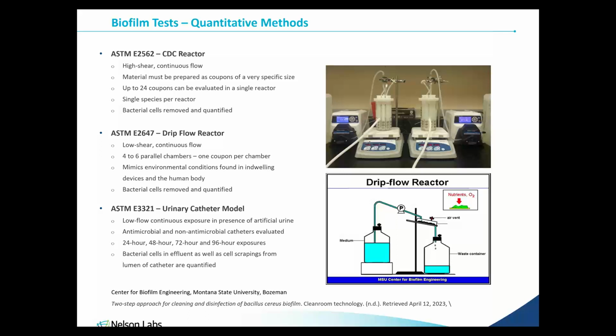In each model, the exposed surfaces are removed from the reactor at a defined time, and the attached bacterial cells are removed by scraping, then diluted and plated. Quantitative recoveries are calculated for each surface. Results can be compared between differing materials, both with and without incorporated antimicrobials. It should be noted that these are not high throughput testing methodologies, and biofilm formation is very species specific. Not all target species can be evaluated using these methodologies. Each of these ASTM methodologies were designed with strains of Pseudomonas aeruginosa.